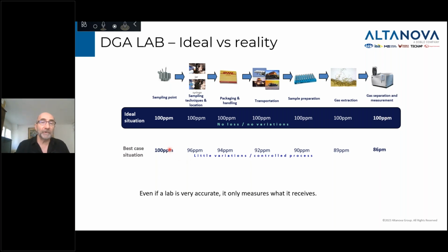But in the best case situation, if you start with 100 ppm and you get a result of around 86 ppm, the whole system accuracy is around 14%. In general, you're still under the IEC spec, and you have a higher probability of doing the right diagnostic using the diagnostic tool. Unfortunately, the worst case scenario we've seen, and we've seen it many, many times, is you start with 100 ppm and you get results of 70 ppm or even worse. And you have to be knowledgeable, or you have to recognize that, because that will have a huge impact on the diagnostic, and will have a huge impact on the decision of what you're going to do.